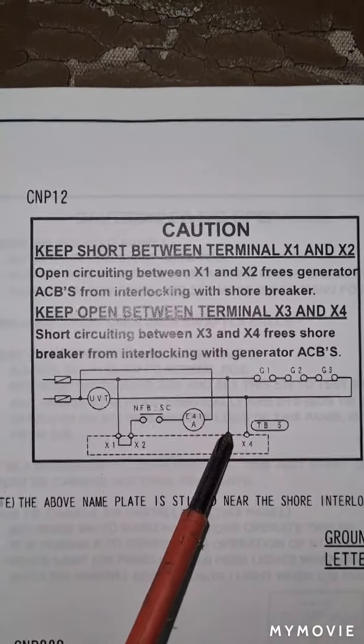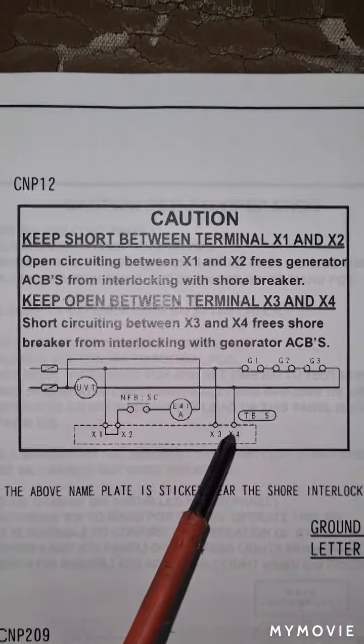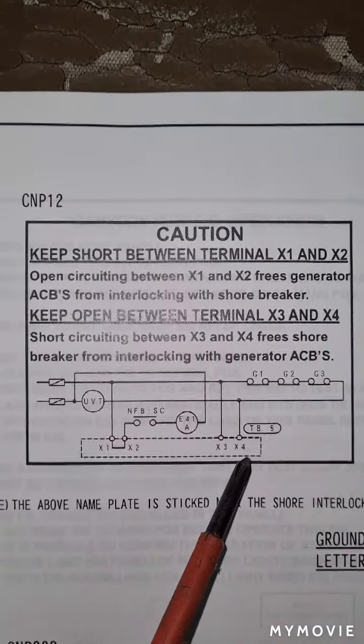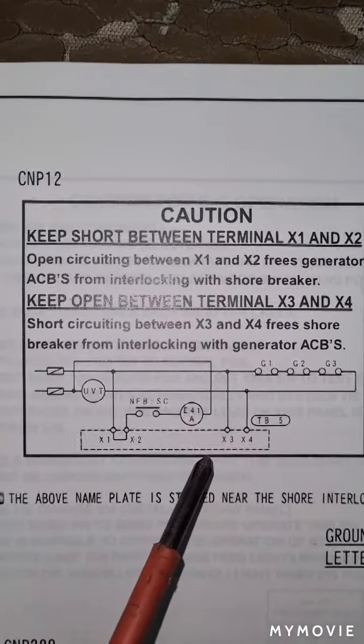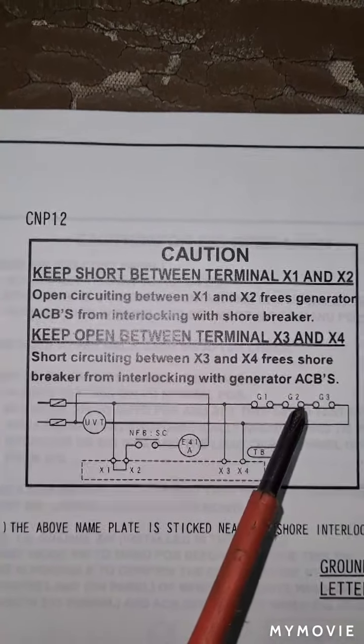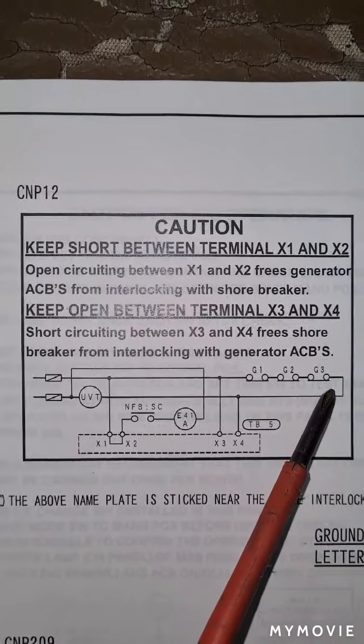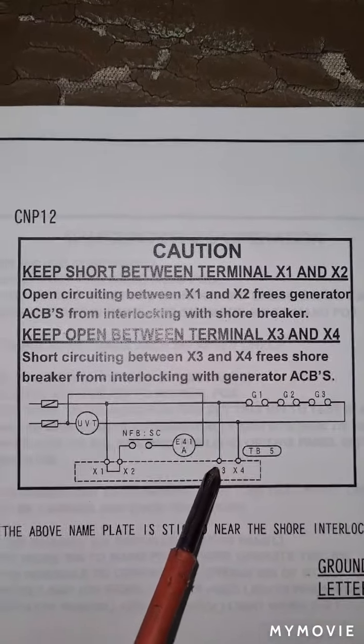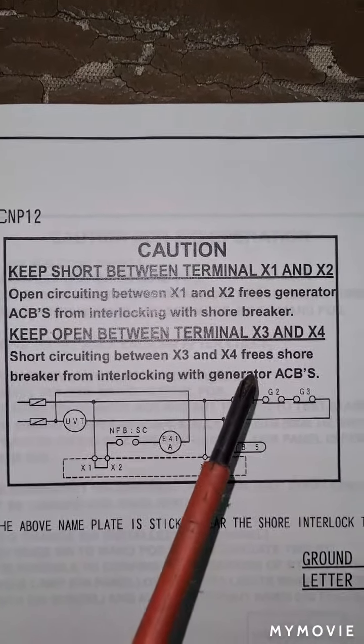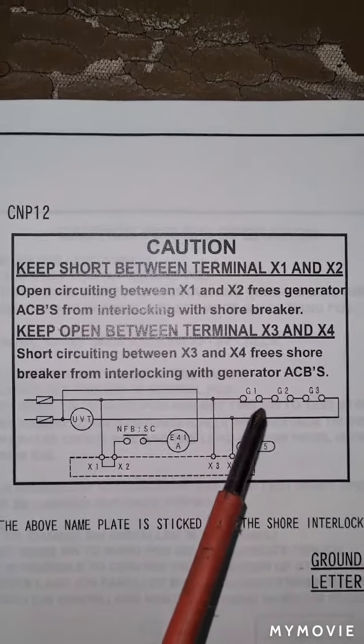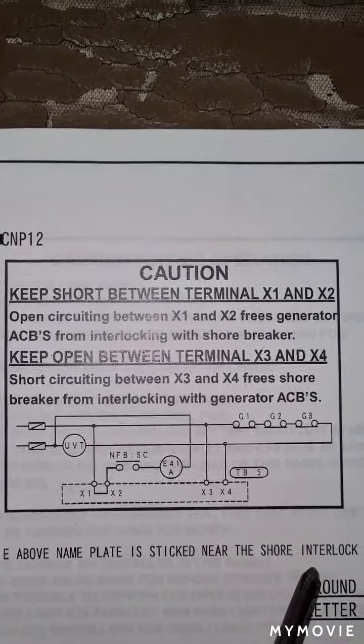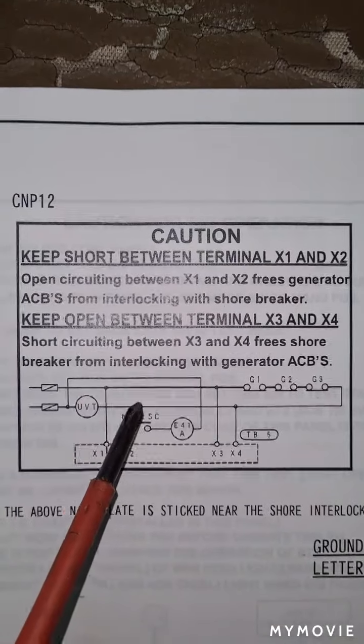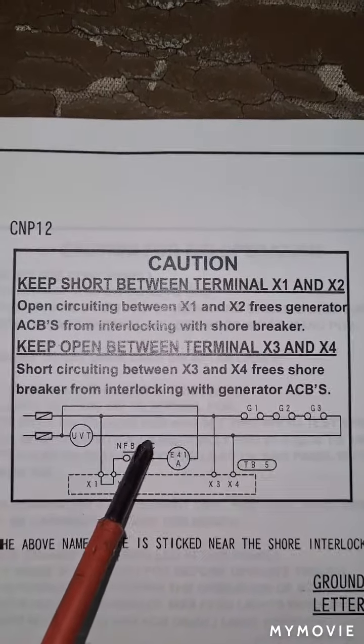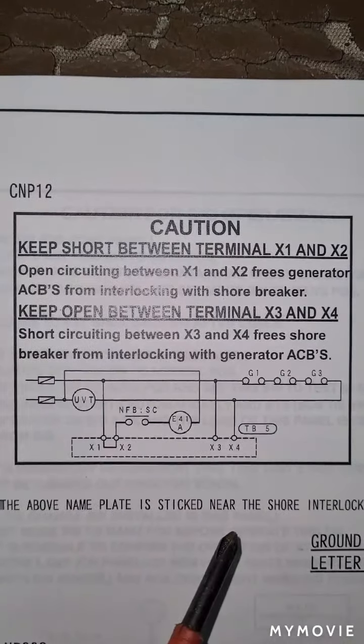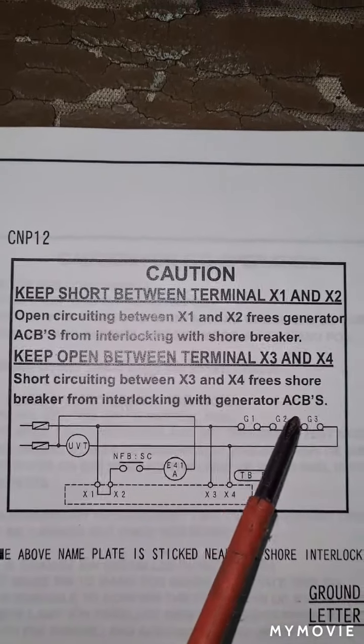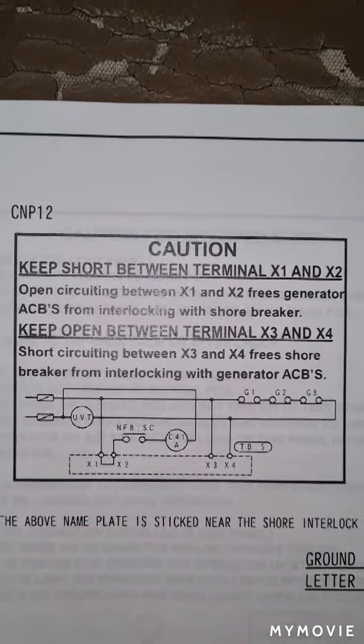Never put a shorting connection wire between X3 and X4, because if you do so, you will also bypass the interlocking system between your shore connection circuit breaker and the G1, G2, G3 circuit breakers. It means if you put a shorting wire on X3 and X4, even if the circuit breaker of G1, G2 or G3 remains switched on, you can still switch on the shore connection circuit breaker. If this happens, it causes problems with your generator systems and the shore power utility.